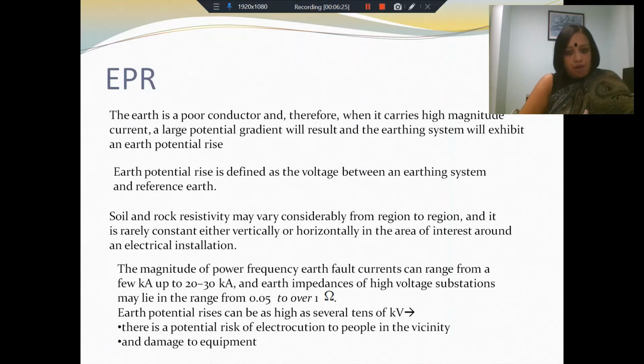The magnitude of the power frequency earth fault currents can range from a few kiloamperes to 20 to 30 kiloamperes. And in the high voltage substation, the earth impedance may lie in the range of 0.05 to more than 1 ohms. So if you look at the resistance, that's a small value. But when you have a very high current flowing, this will cause a very high earth potential rise. This earth potential rise, or EPR, can be as high as several tens of kilovolts. And several tens of kilovolts is dangerous to anything around it.